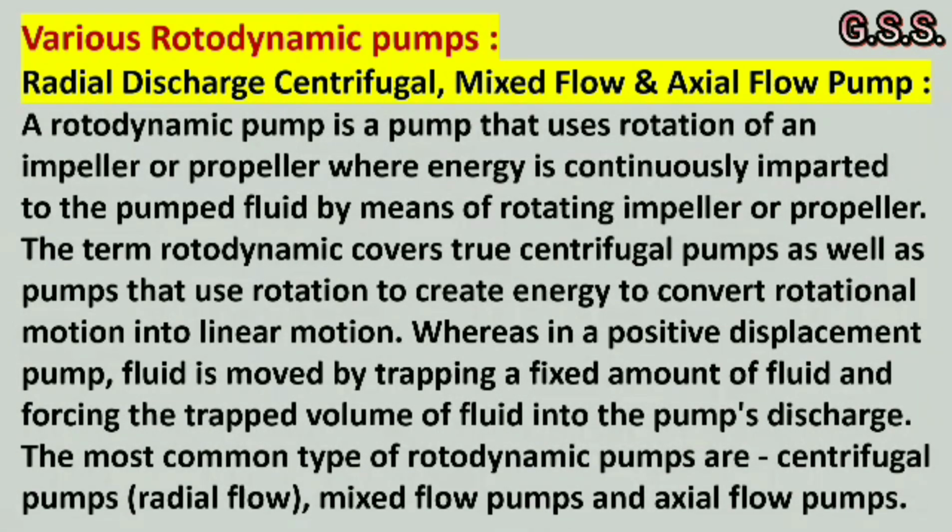A rotodynamic pump is a pump that uses rotation of an impeller or propeller where energy is continuously imparted to the pumped fluid by means of rotating impeller or propeller. The term rotodynamic covers true centrifugal pumps as well as pumps that use rotation to create energy to convert rotational motion into linear motion. Whereas in a positive displacement pump, fluid is moved by trapping a fixed amount of fluid and forcing the trapped volume of fluid into the pump's discharge.